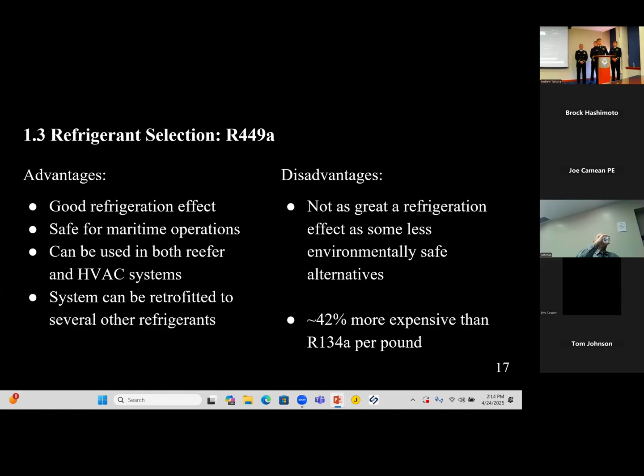And that brings us to our final selection, which is R449A. Now, this has several advantages. It has a good refrigeration effect. It's safe for maritime operations compared to other refrigerants. It can be used in both the HVAC and reefer systems. And most importantly, the pressures and temperatures it operates under can mean the system can be easily retrofitted to other refrigerants. And I'll get back to that in a minute.